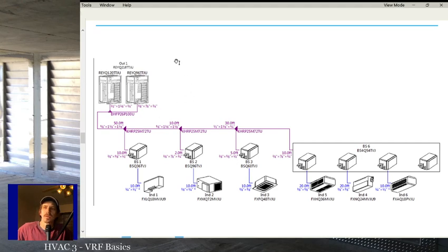So outdoor unit is pretty similar. The only difference on the outdoor units is when you had multiple, Daikin and I think a couple other manufacturers used to require an oil equalization line between outdoor units, but they no longer require that. They've gotten around that, and that is one big problem when you're talking large systems, or VRF in particular. Oil return is a huge problem. That's one of the biggest problems they have to overcome when they design these systems.